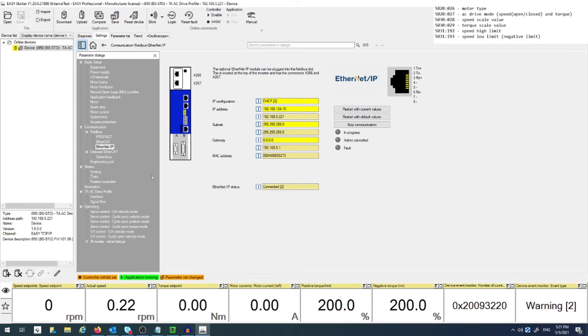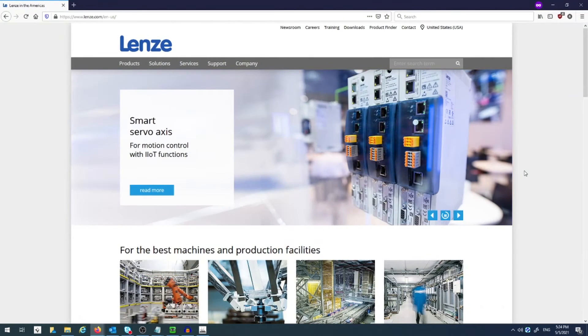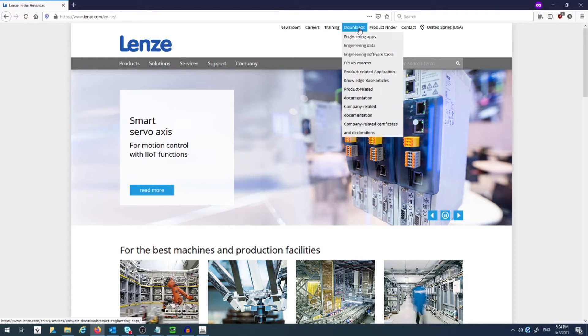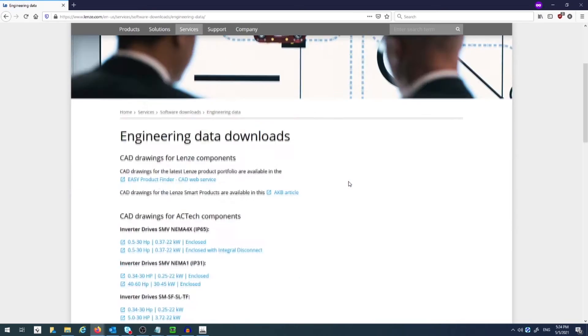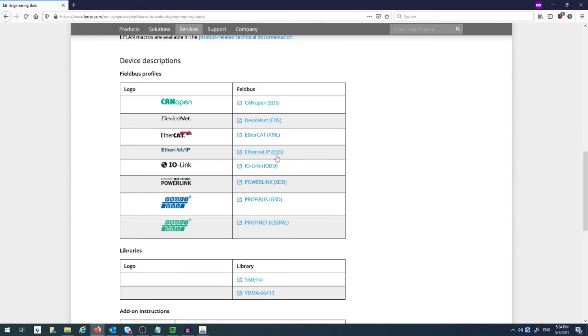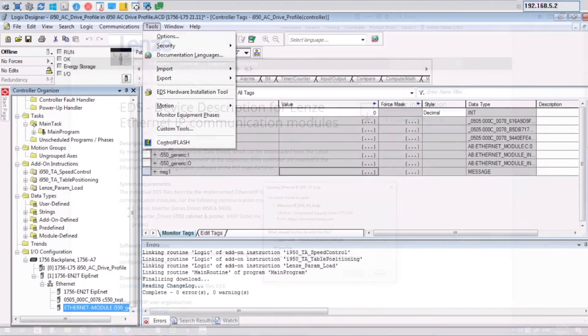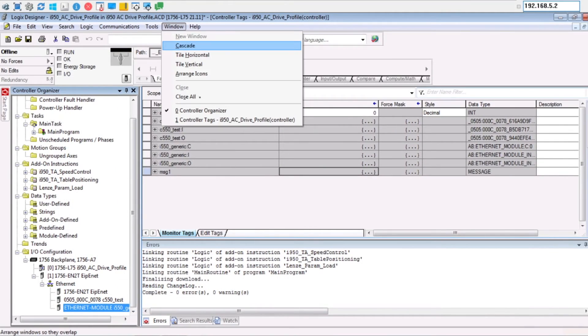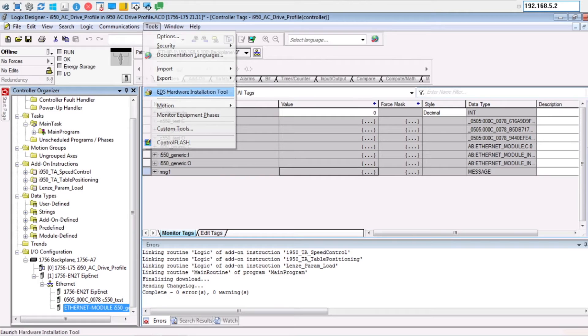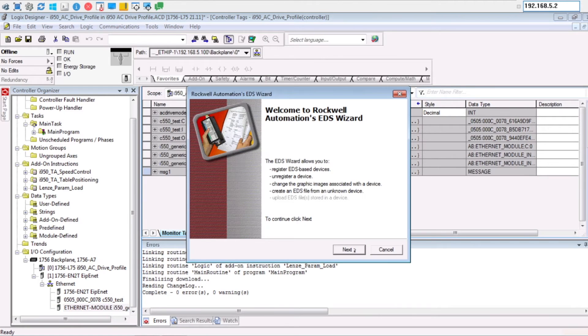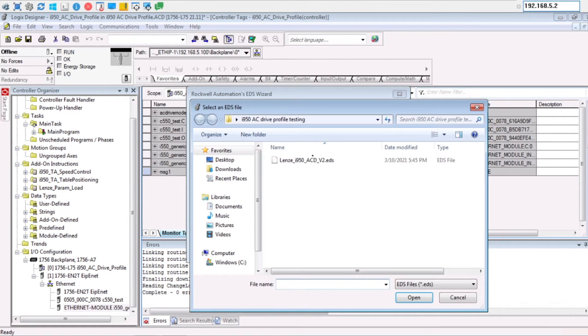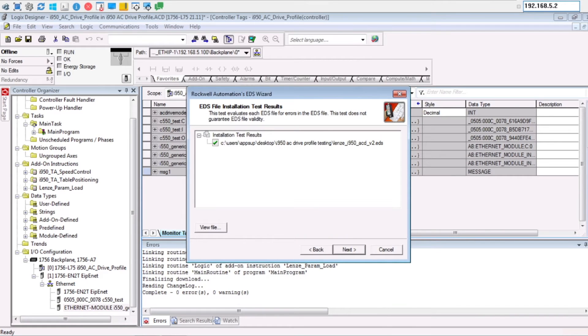Now let's move on to the PLC side. You should have an Ethernet IP EDS file downloaded from the Lenze official site. This can be found in the Engineering Data tab of the Downloads section. Afterwards, install the EDS file using the EDS hardware installation tool. The Rockwell software should now be able to recognize the i950 as a device.